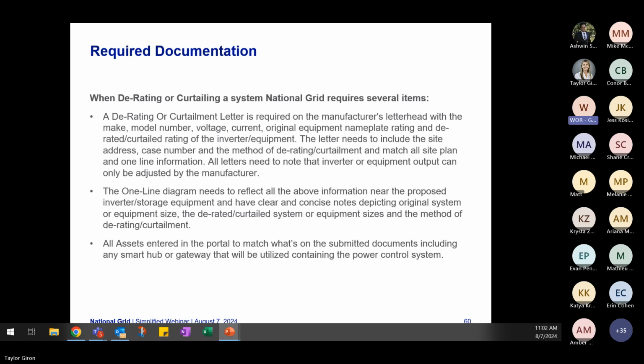The required documentation. So when derating or curtailing a system, National Grid requires several items. A derating or curtailment letter is required on the manufacturer's letterhead with the make, model number, voltage, current, original equipment nameplate rating, and derated or curtailed rating on the inverter equipment. The letter needs to include the site address, case number, and the method of derating or curtailment, and match all site plan and one line information. All letters need to note that inverter equipment output can only be adjusted by the manufacturer. Please also make sure all this information is on the one line and all the assets are entered correctly onto the portal along with the PCS equipment. Next slide, please.